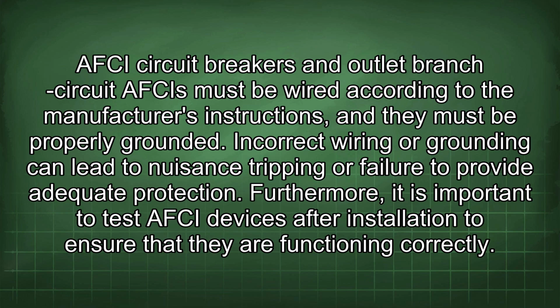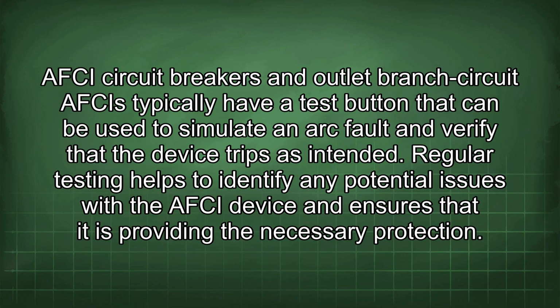Furthermore, it is important to test AFCI devices after installation to ensure that they are functioning correctly. AFCI circuit breakers and outlet branch circuit AFCIs typically have a test button that can be used to simulate an arc fault and verify that the device trips as intended. Regular testing helps to identify any potential issues with the AFCI device and ensures that it is providing the necessary protection.